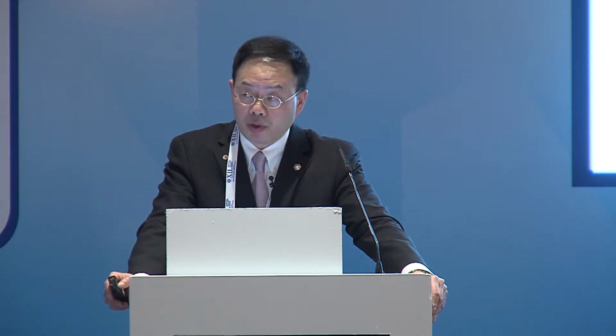One very important question right now facing ASHRAE, IEST, and also our European counterparts is how to determine the quantity of the airflow. So let me give you some background information. First is the comparison with a general purpose room. For commercial buildings, typically in the US, possibly in the rest of the world, 70–80% of buildings have air changes per hour possibly within 6 up to 25. Some could be higher, some could be lower. The purpose is to meet the heating and cooling loads and the ventilation load requirement.